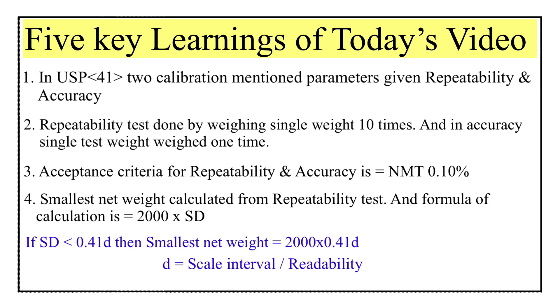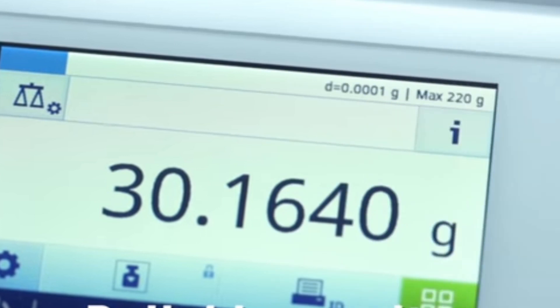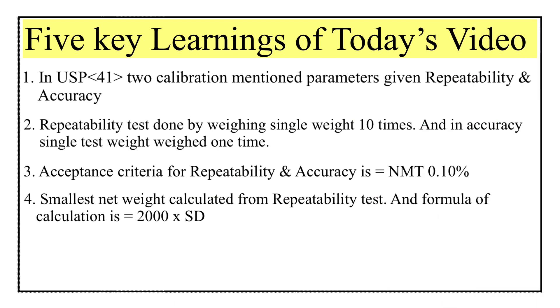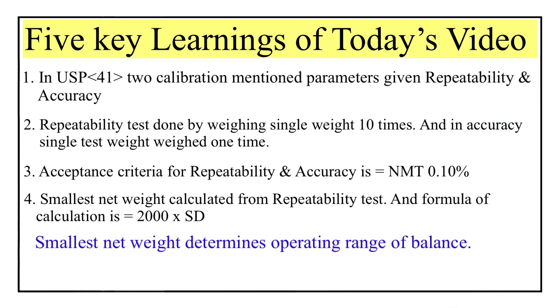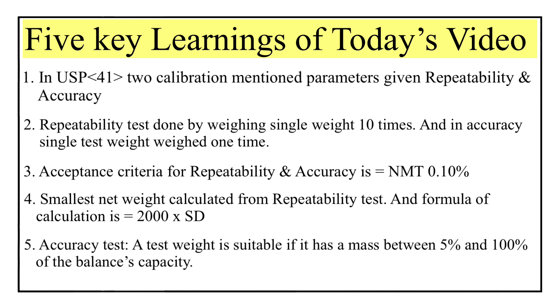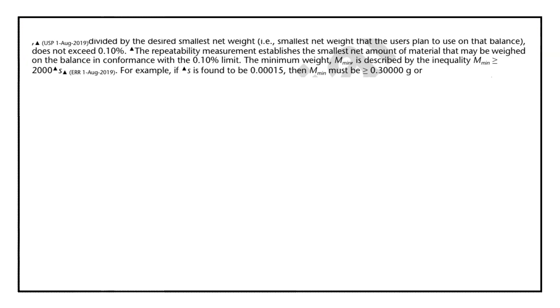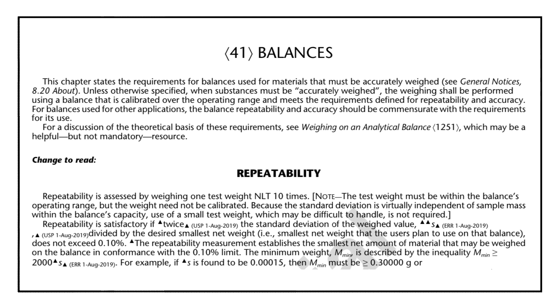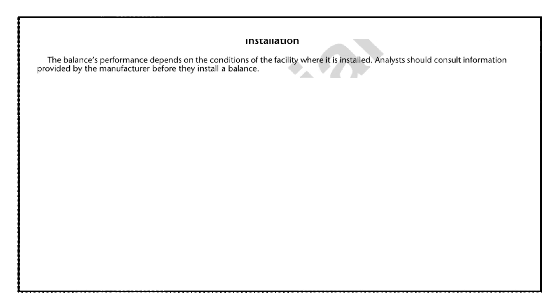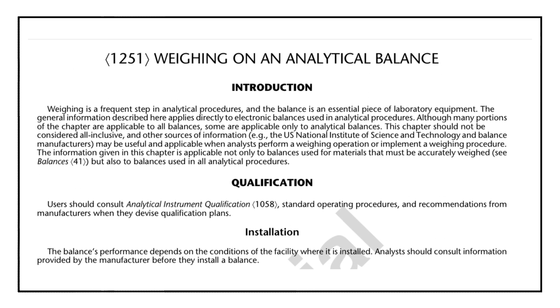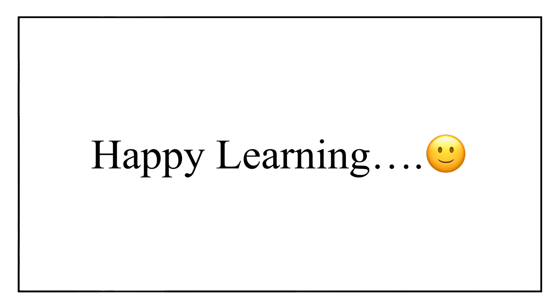Next time whenever you do weighing in the lab, check your balance screen carefully — you will find a d value displayed on the balance screen. Smallest net weight helps us in determining the operating range of a balance. Point five: to carry out the accuracy test, the test weight should be between 5 to 100 percent of the balance capacity. That was all about today's video — hope you learned something new. In the next video we will decode USP General Chapter number 1251. Till then, stay tuned to Pharma Pill. Bye-bye and happy learning.